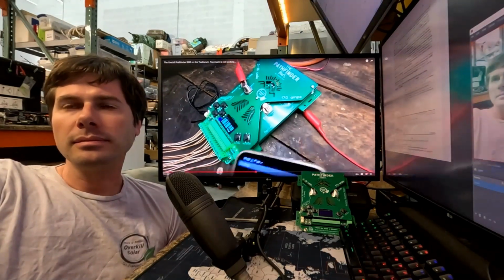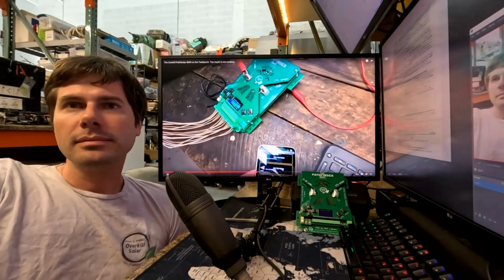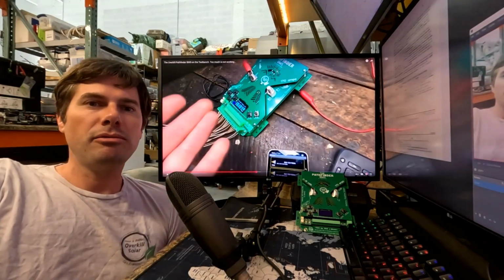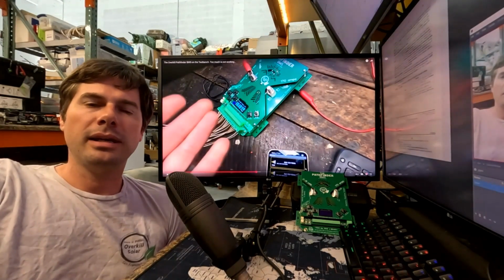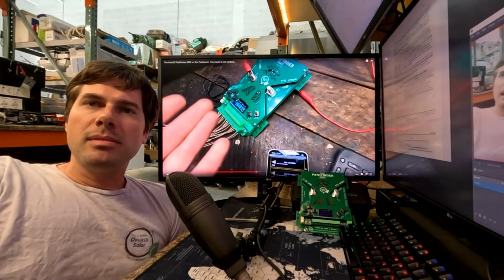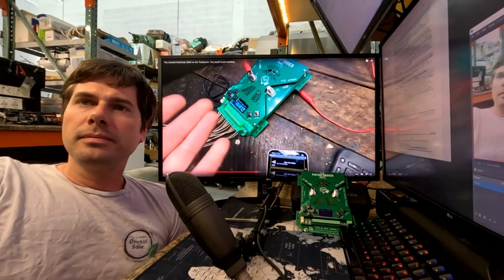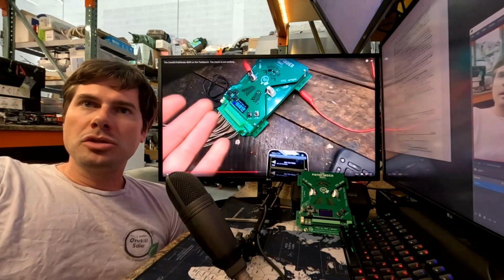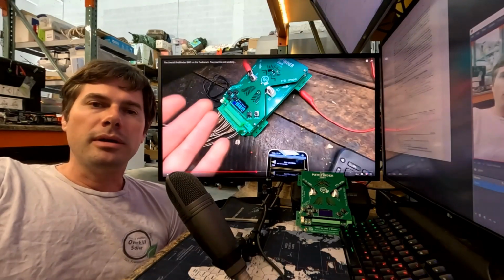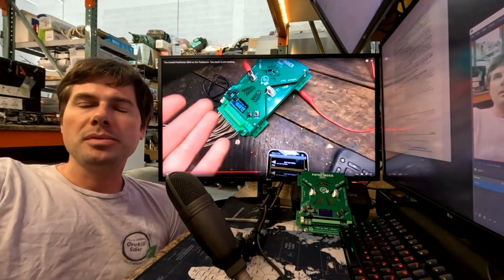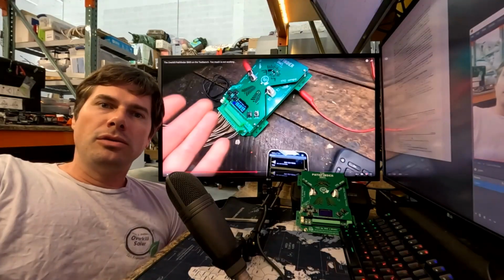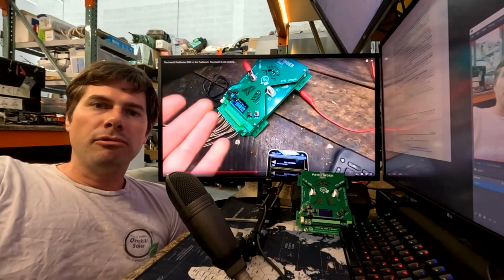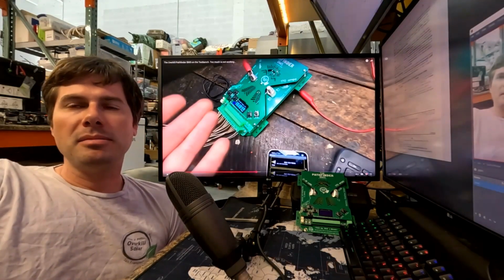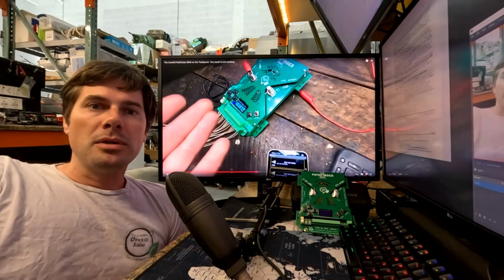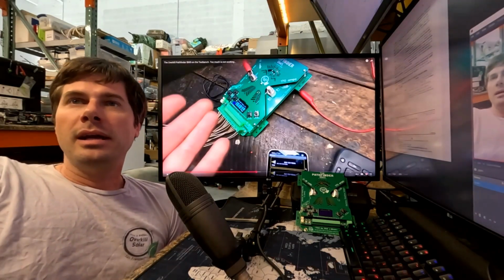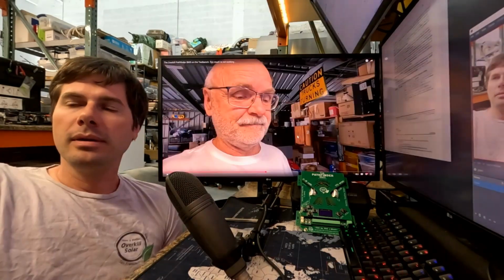There's nothing connected, but the BMS claims we are discharging. It's really difficult because it's an analog circuit that has to measure accurately up to 400 amps, so you're asking the same circuit to measure 12-20 milliamps and 400 amps at the same time. There's a lot of noise floor - I should just increase the deadband.